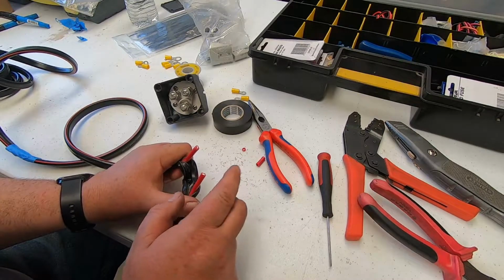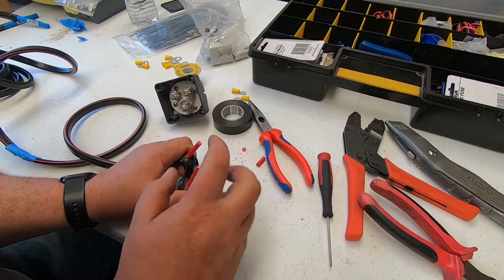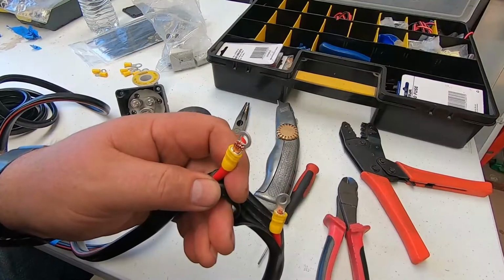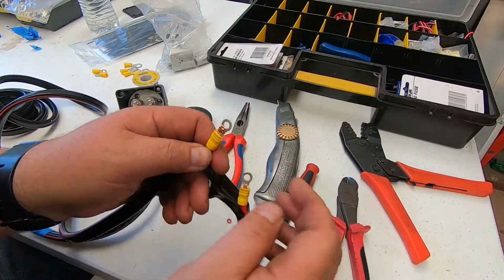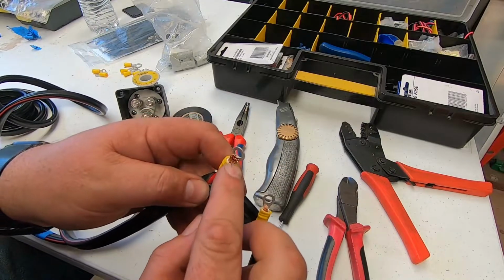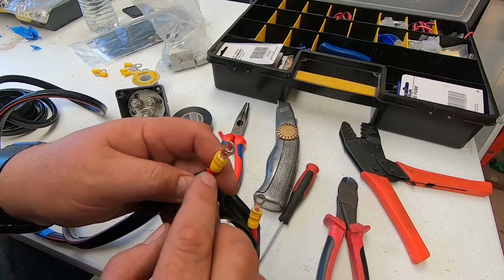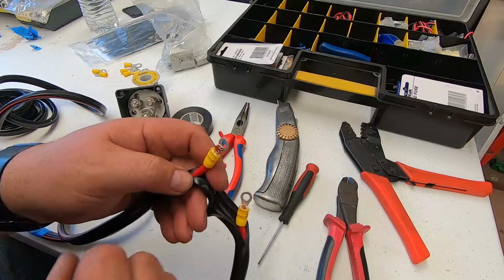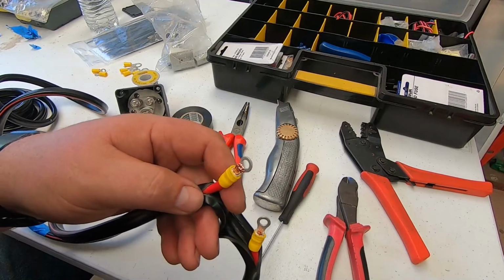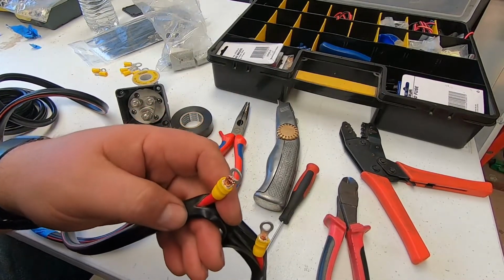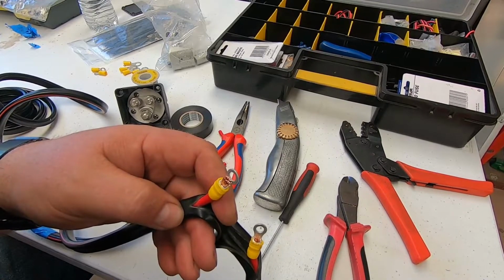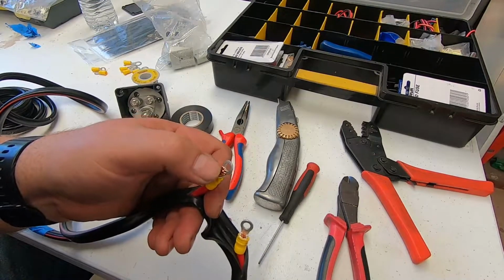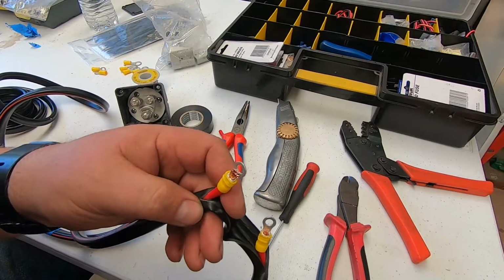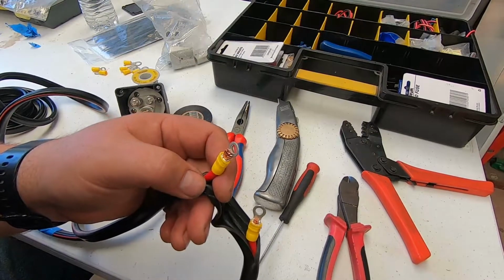So all we'll do is strip these off, crimp the ends on, and that's where the breaker is going to go. Same again, you can see there's a fair old mouthful of cable there, all the strands have gone all the way through. I'll trim them off a bit and solder the ends now. But that's probably the maximum amount of cable thickness you can get in these connectors. At least you know that 100% of the strands are in there, so it'll allow full current flow.